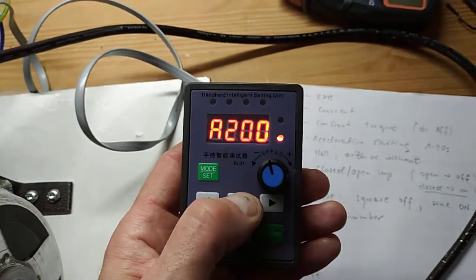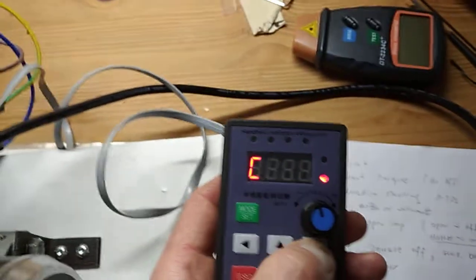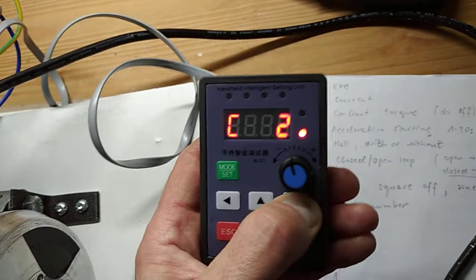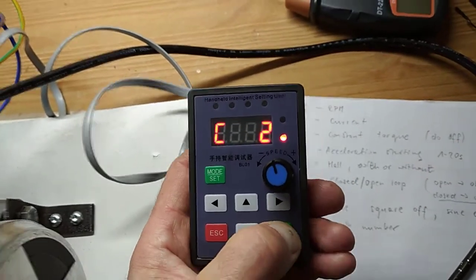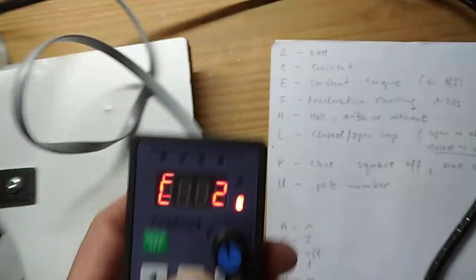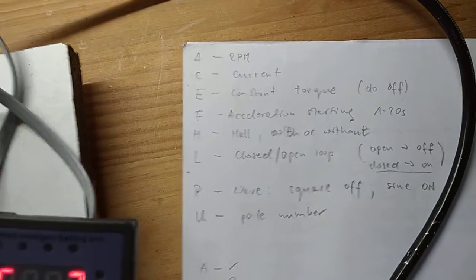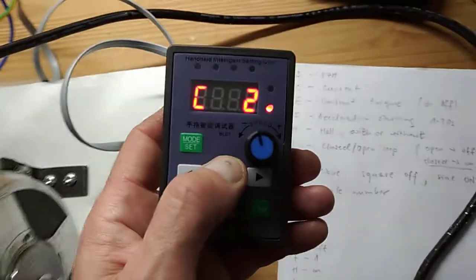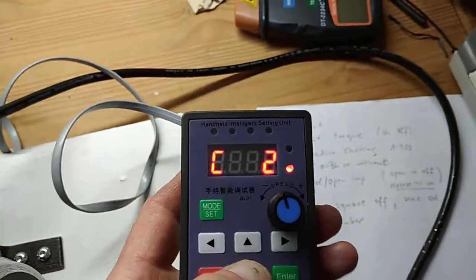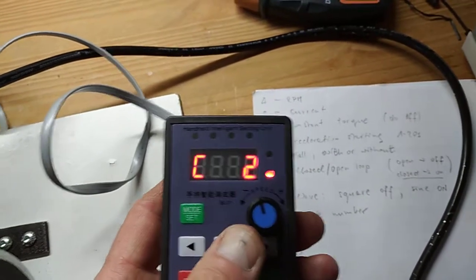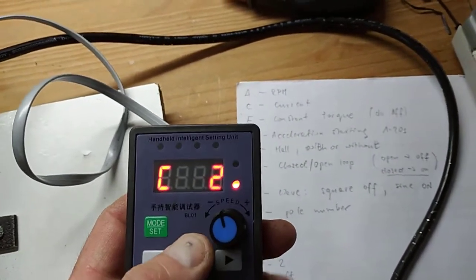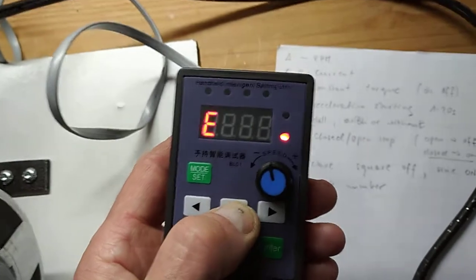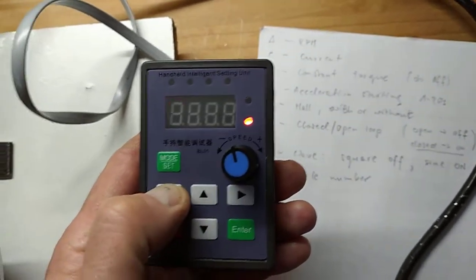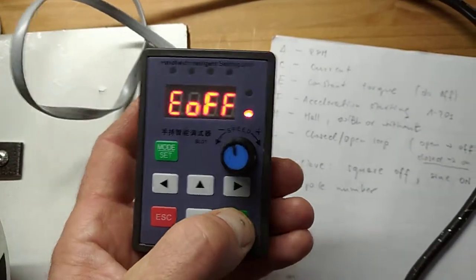Okay. Next is C, which is current. This is a small motor, so let's say 2 amps. Enter. Good. Next one is constant torque. In the description they say you don't want to run your motor on constant torque all the time, so we will set it to off.